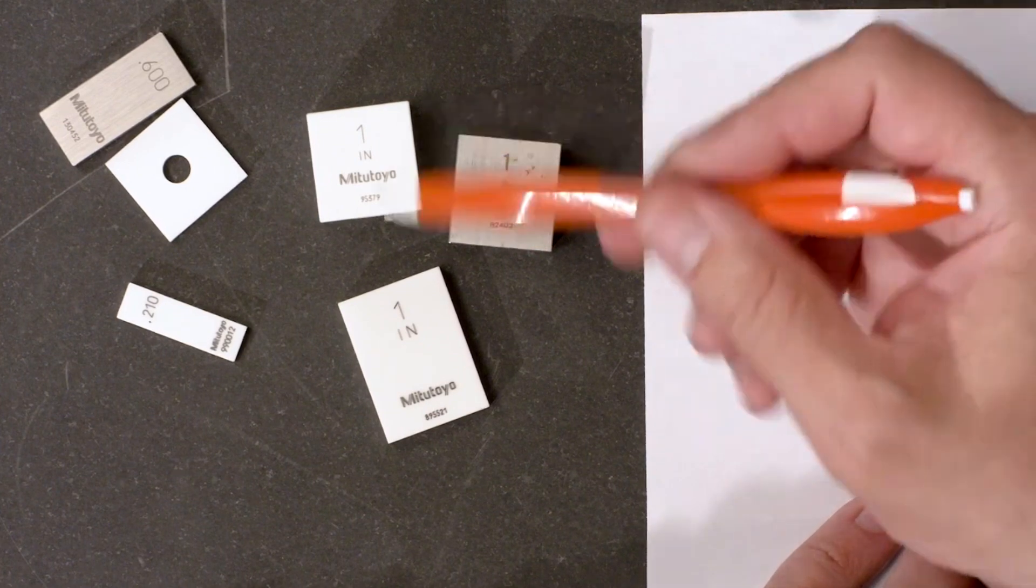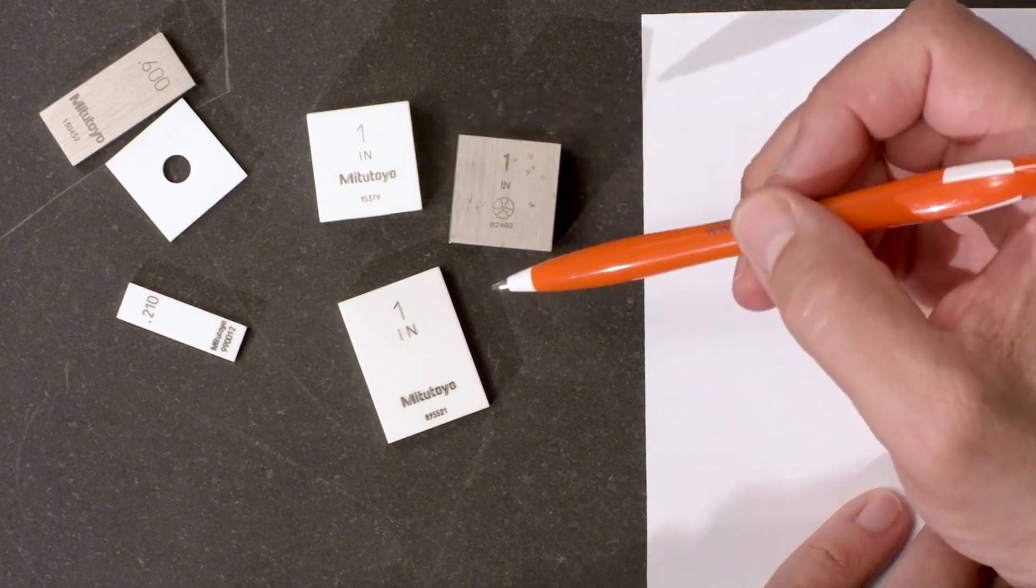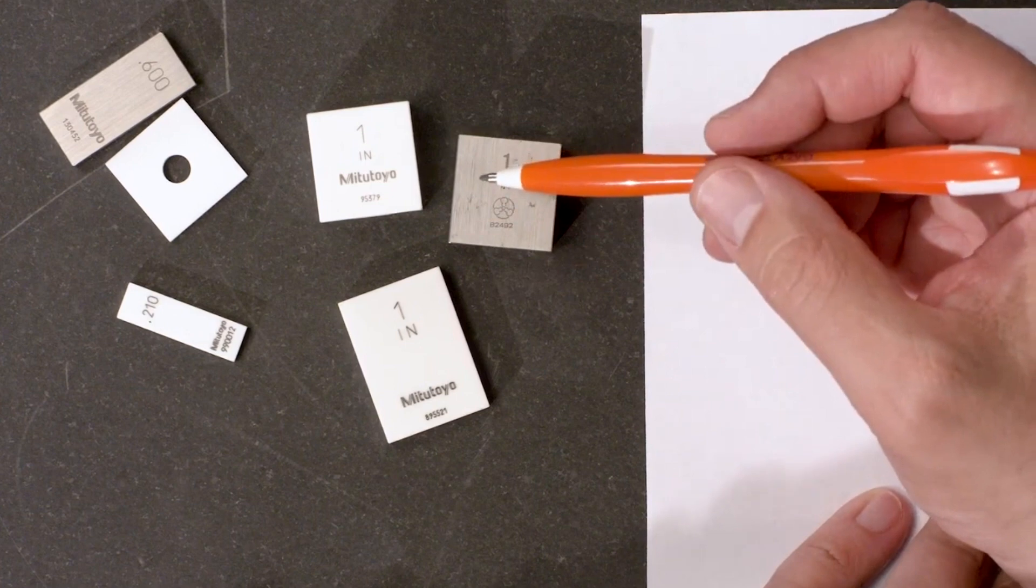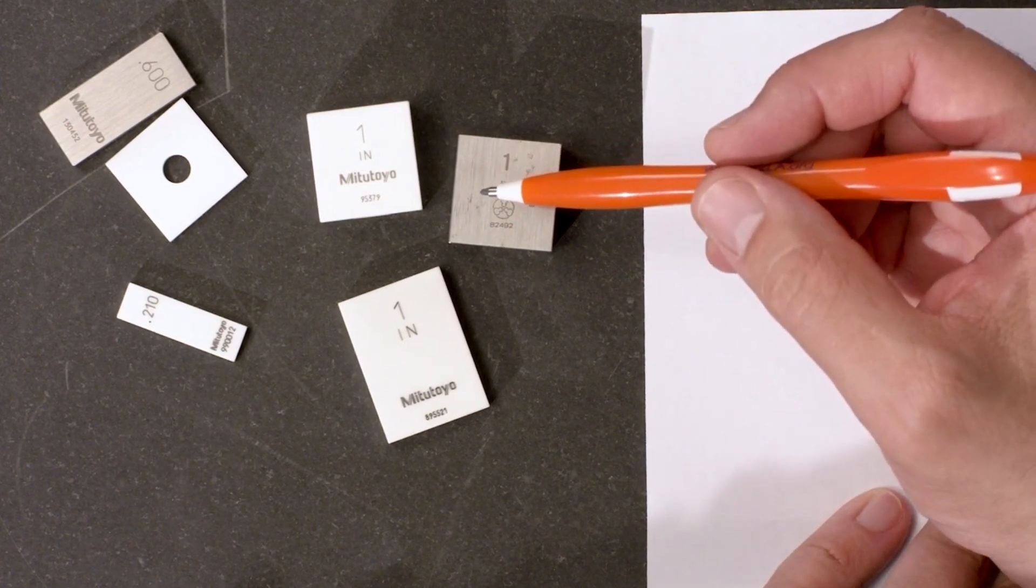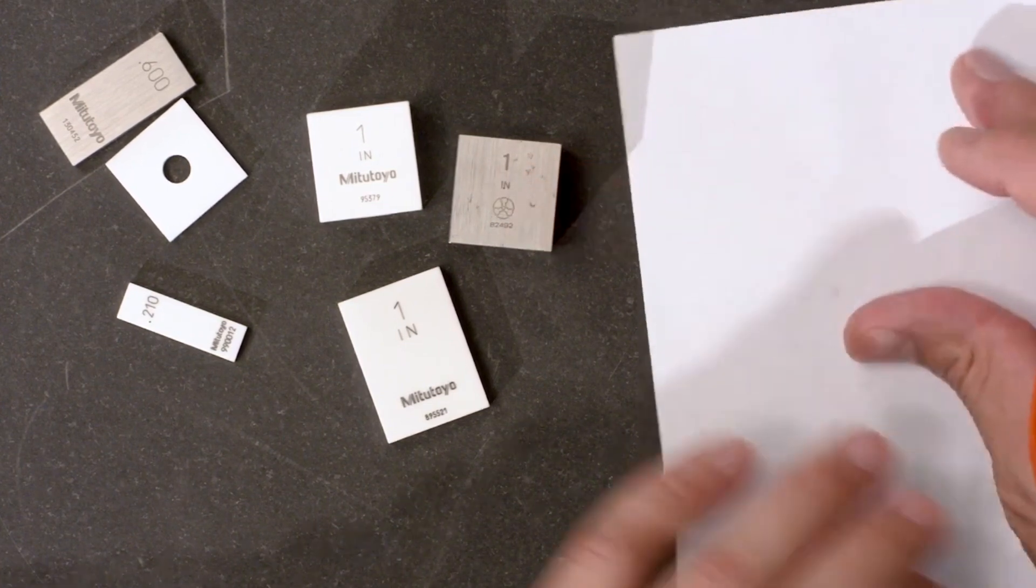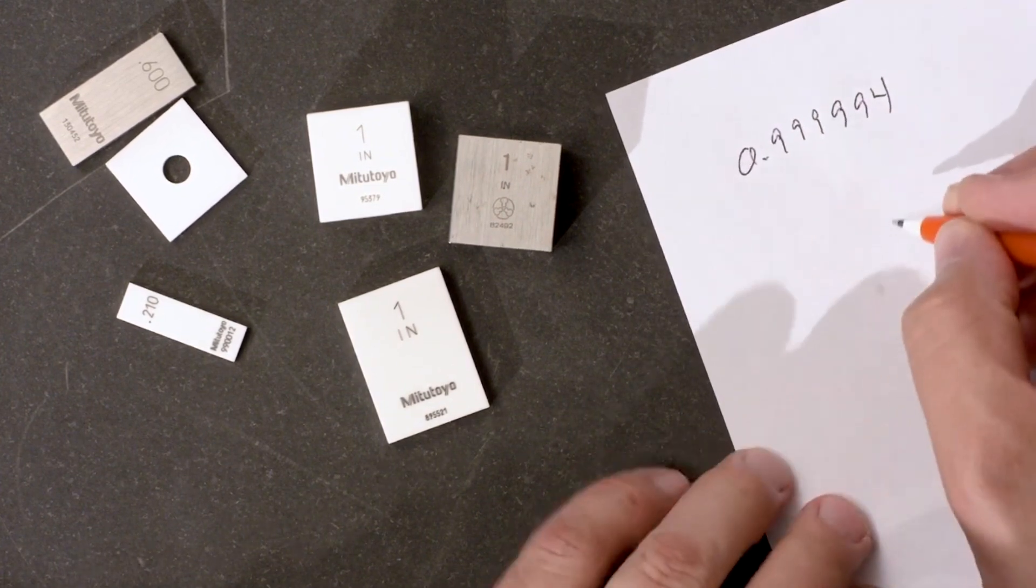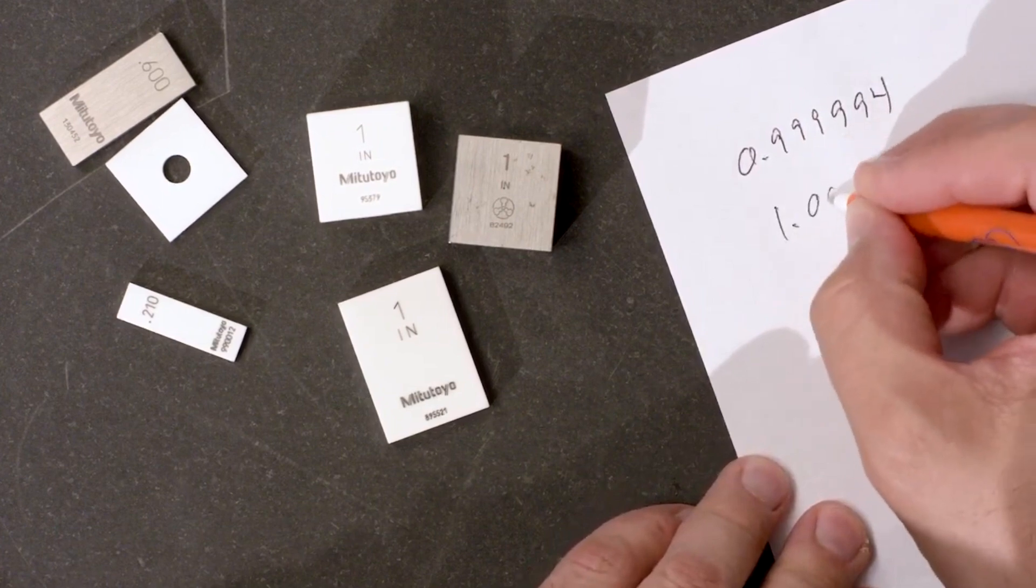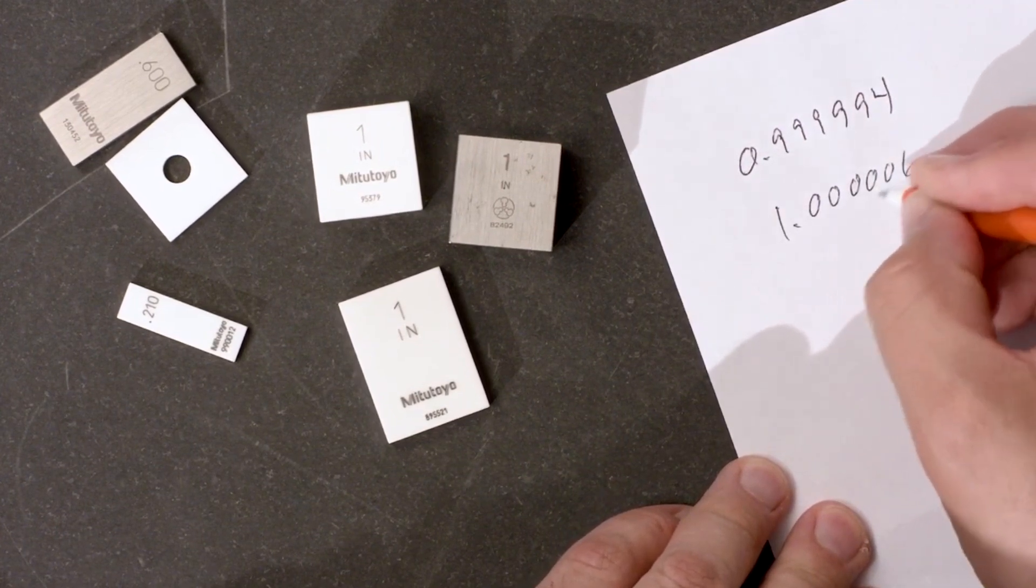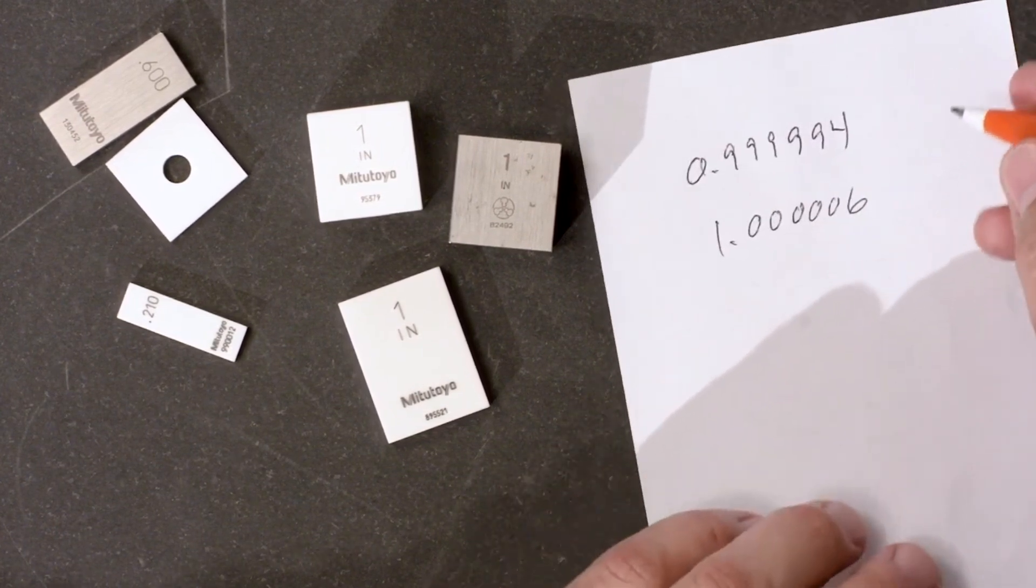If this Gauge Block or all three of these Gauge Blocks have been properly calibrated and found to be in tolerance, then I would know that the length is somewhere between the minus 6 millionths and the plus 6 millionths of an inch.